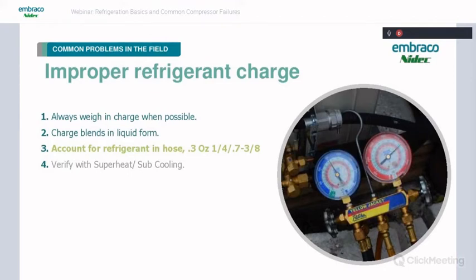And you can also account for the refrigerant in your hose. It's about 0.3 ounces per foot for a 1/4 inch hose, and 0.7 for a 3/8 hose. That's for R22. It's going to be a little bit different with different density refrigerants. Basically, if you measure the correct charge through your scale, and then you close off your valves and start up the system, you can meter in the rest of the charge through the charging and the suction line, and that should basically ensure that you're getting almost the exact charge in there. And you can also verify it with either superheat or subcooling. We'll talk a little bit more about that in a little bit.